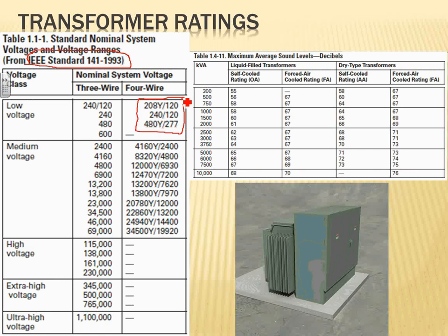In the medium voltage world, which some of you use, probably a lot of us are engaged up to this level. You'll see this a lot, from 4160 all the way to 138. These are different levels. The most common ones used as feeders are 1247, 13.2, 13.8, and 4160.